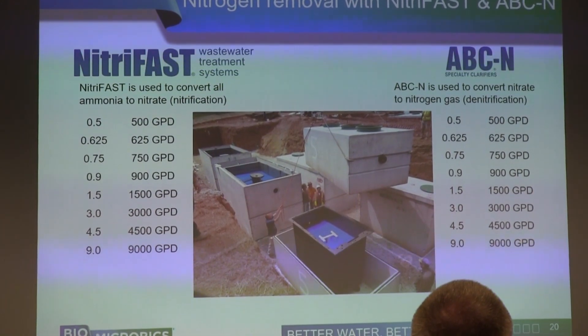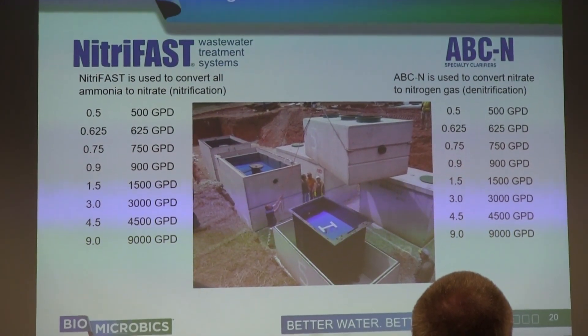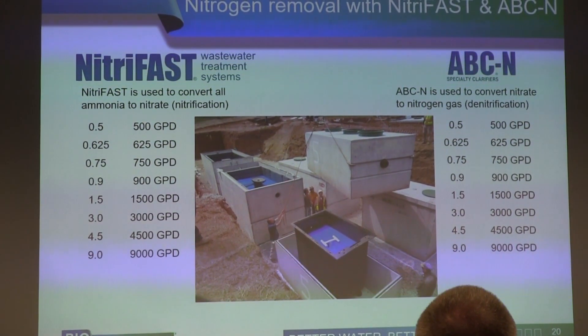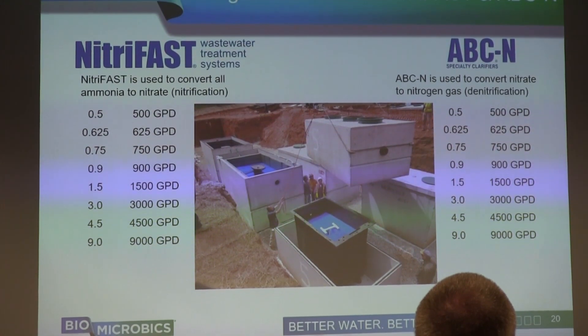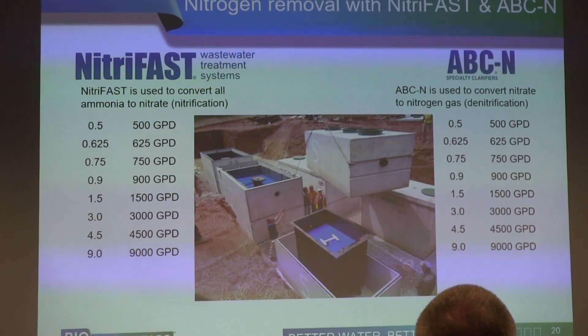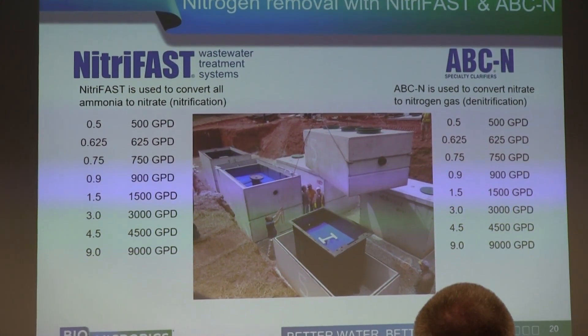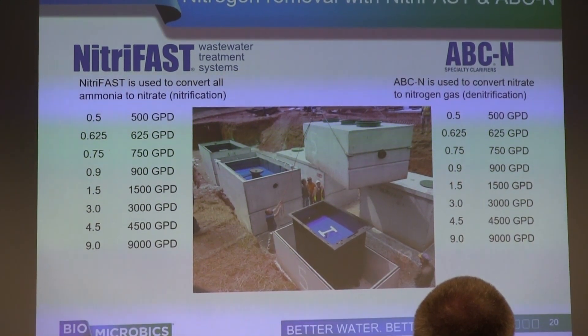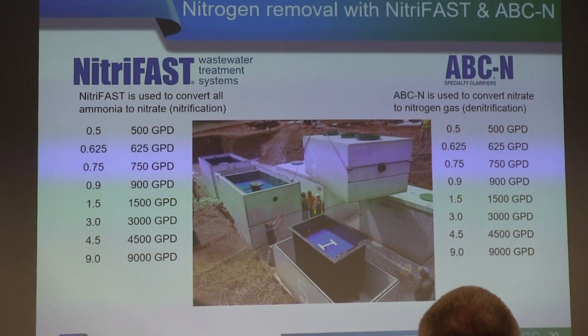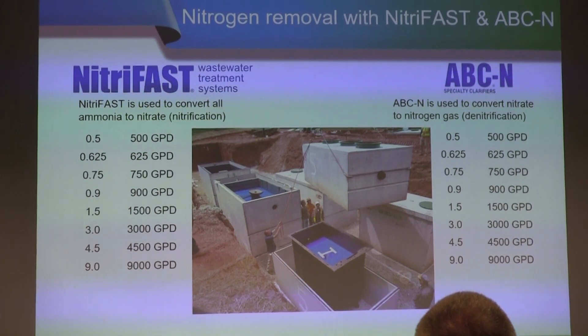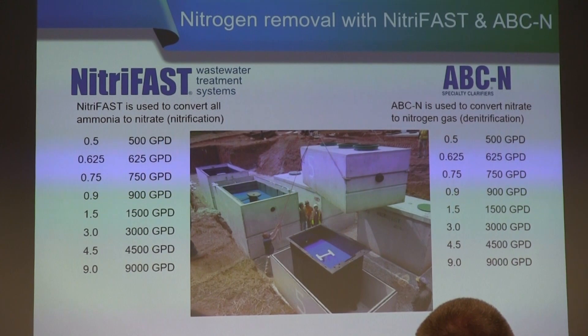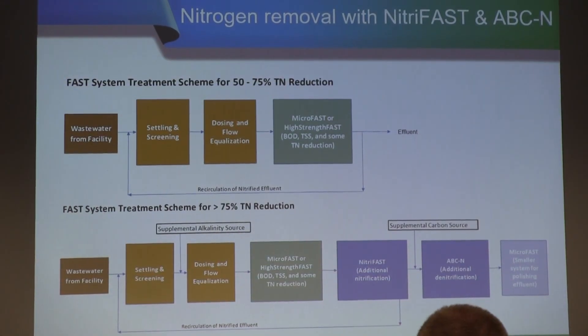The model sizes for NitriFAST and ABCN match up with the model sizes for Micro FAST and high-strength FAST — roughly speaking, they're rated for the same gallons per day. However, we size each one based on a number of factors, which is why we want to work with you to select them. We'll need to know the climate, estimated wastewater temperature, and the influent and effluent estimates for nitrogen to properly select the combination of systems.